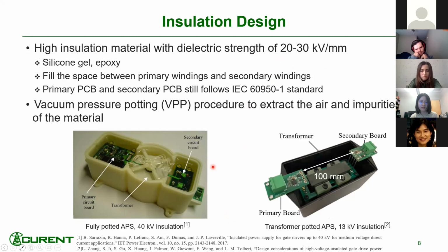And the materials used are silicone gel or epoxy, depending on the application. It just needs to fill the space between the primary windings and the secondary windings. As you can see here in this picture, there will be a transformer and the PCBs are connected to the windings.